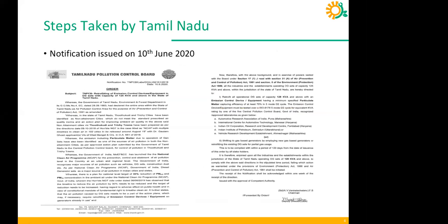Not only this, Tamil Nadu on 10th of June also came out with a government order, a state notification stating again that any DG, if you have a DG of capacity 125 kVA and above, you have to retrofit it with an emission control technology. Also, what they further clarified was that the retrofit control technology should be tested under ISO 8178-4 (D2 cycle) for equivalent kVA from any one of the 5 CPCB recognized labs, and these were the 5 labs that they mentioned. Or the other option is still available, that you can shift to a gas-based generator, discarding your DG absolutely.